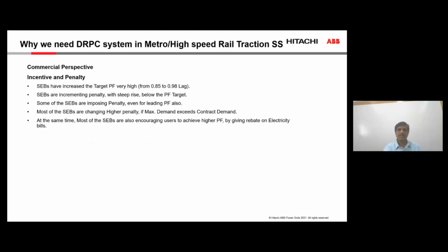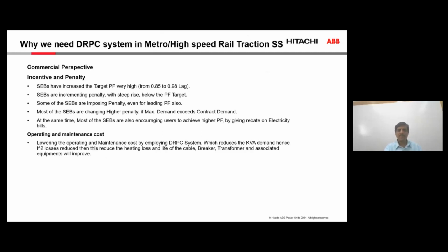We are calculating this on an annual basis. It comes to a very, very big sum as compared to the investment that is required for the dynamic system. So when we look at the electricity bill, that's one aspect. The other aspect is from an O&M perspective. The operation and maintenance person is looking at this. What does he see? He sees that there is a reduction in kVA, therefore a reduction in losses and a reduction in heat. Therefore, he sees that the breakers, the transformer, and the associated switchgear equipment have improved life and quality.